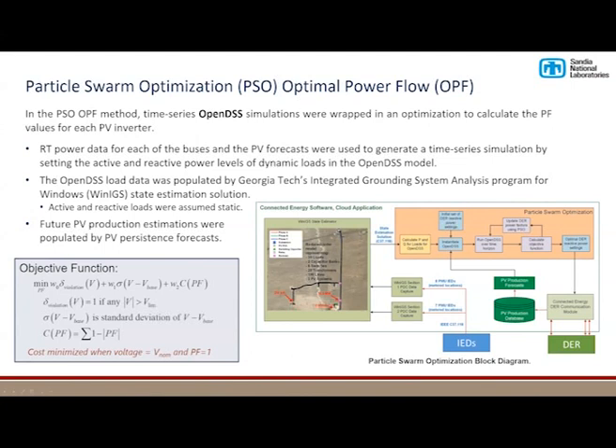And the objective function that we're trying to minimize is shown here. Essentially, we wanted to minimize cases where we're exceeding the ANSI limits. You minimize that essentially when you get closest to the nominal voltage and a power factor of one. And the power factor component is some crude method of considering the economics of it. If you're operating off a unity power factor, you're potentially not producing as much real power and therefore not generating as much money for the customers.